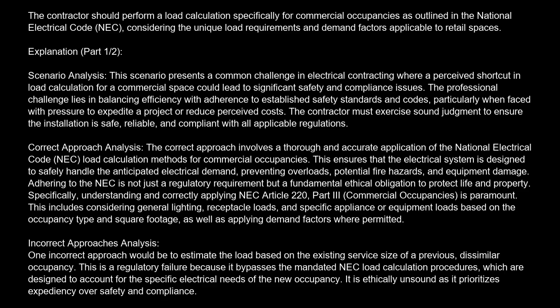Correct approach analysis. The correct approach involves a thorough and accurate application of the National Electrical Code, NEC, load calculation methods for commercial occupancies. This ensures that the electrical system is designed to safely handle the anticipated electrical demand, preventing overloads, potential fire hazards, and equipment damage. Adhering to the NEC is not just a regulatory requirement but a fundamental ethical obligation to protect life and property. Specifically, understanding and correctly applying NEC Article 220, Part III, Commercial Occupancies, is paramount. This includes considering general lighting, receptacle loads, and specific appliance or equipment loads based on the occupancy type and square footage, as well as applying demand factors where permitted.